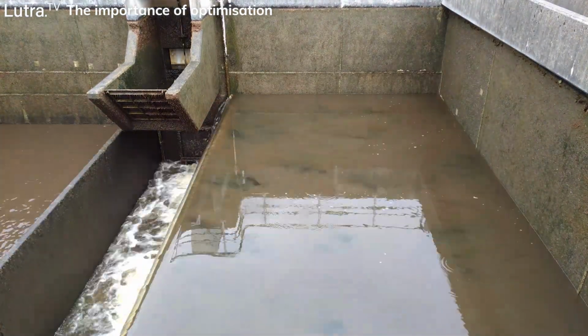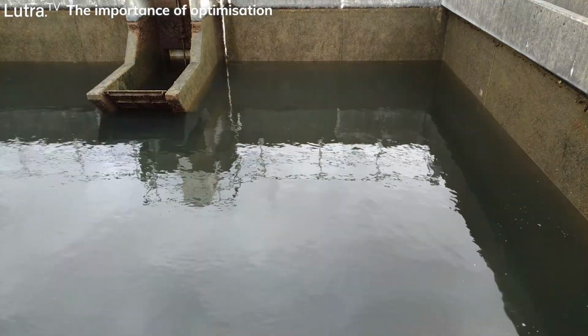So the cause of that performance might be anything. It might be the way the plant flow is controlled, causing carryover. It might be the type of polymer that's used, causing the floc to rise up too much, or the dose rate of that polymer. It might be the coagulant dose rate. There's a lot of different things, but whichever one it happens to be, tweaking it just right means that you may save money on the chemical being dosed, but also reduce the effect on the downstream. And in some cases, you might even improve the performance of the turbidity off those filters.